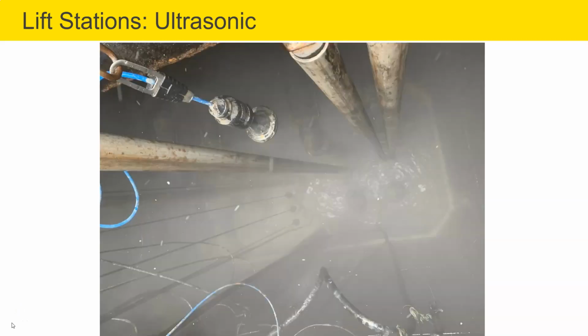Steam, condensation, fog, and this kind of fog from the humidity is a huge problem in lift stations. Not a problem with radar. When we first opened this lift station up, it took 10 minutes for the condensation to clear to get this picture. The humidity was that thick.